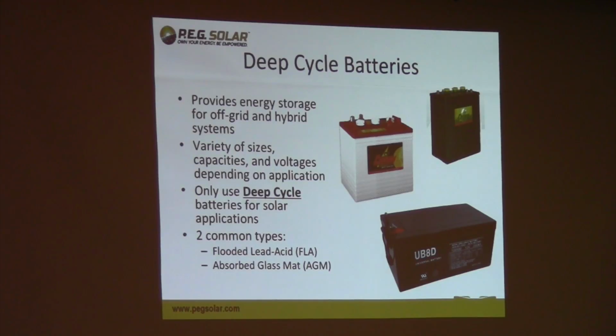In AGM batteries, the electrolyte is immobilized in a fiberglass mat inside the battery, so it doesn't slosh around. These are very popular in boats or places where the battery may be tossed around or has to be placed on its side. They're also much safer for indoor use because they don't off-gas hydrogen as badly as a flooded battery does. A flooded battery pretty much has to be used outdoors, or in a container with direct ventilation outdoors, so you don't get that hydrogen gas buildup.